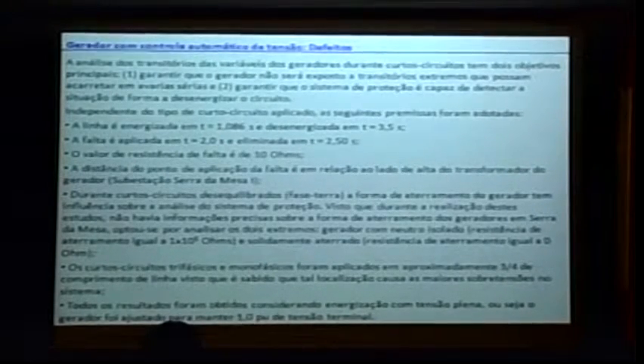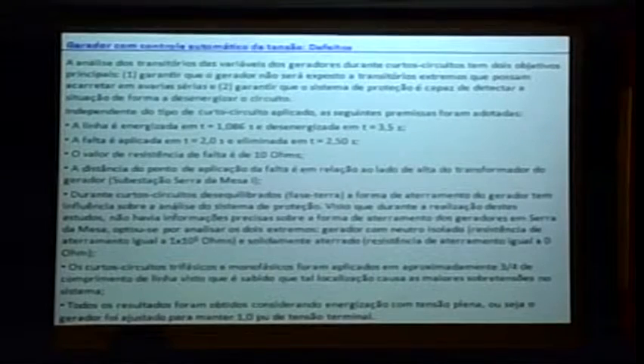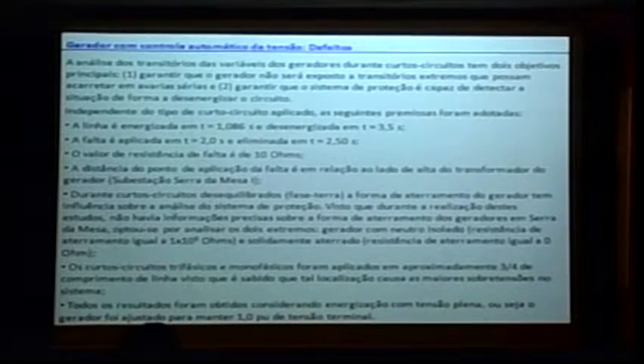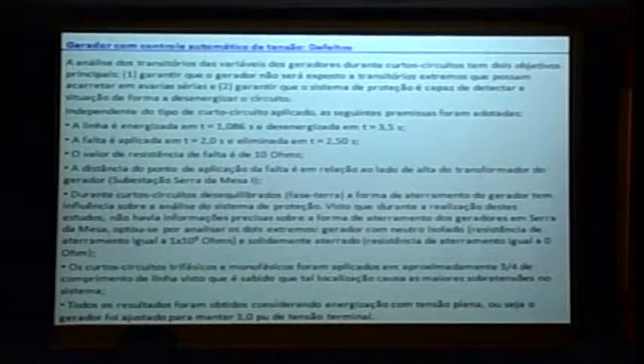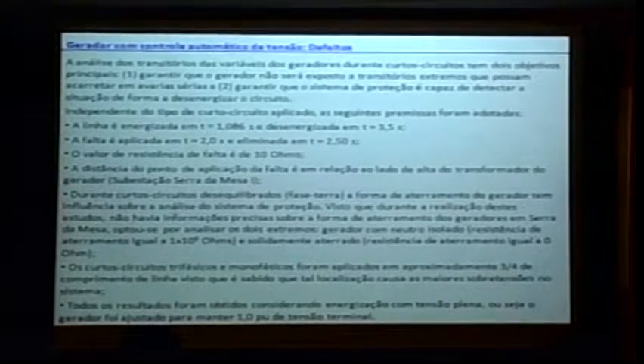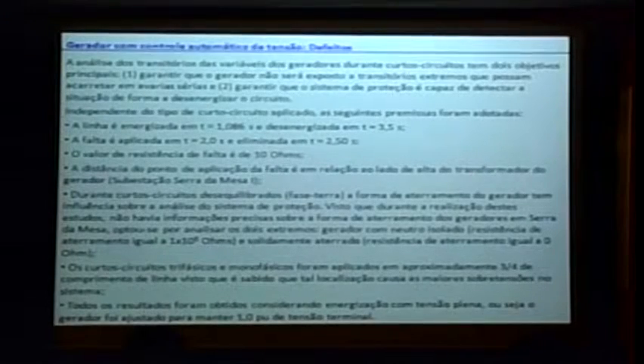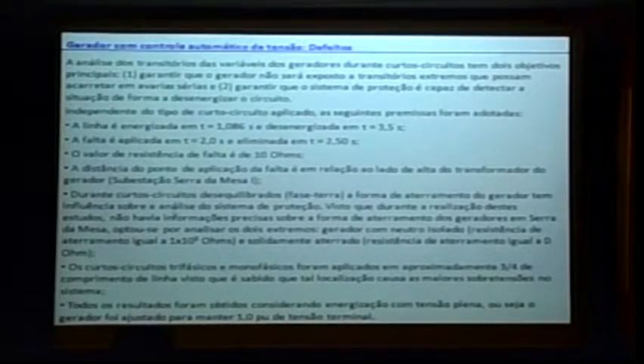During the energization, after a while you see that it stabilizes. You make a fault to see what happens to the generator in case, for instance, there were faults during the energization test of the line with half wavelength, single phase and three phase. That was the scanning of the whole extension of the line, but I'm going to show you here only around 3/4 of the line. The fault is always applied in 2 seconds and it's eliminated in 2.5 seconds. So we will keep the fault for 500 milliseconds, precisely to analyze what impact it has on the generator. Fault resistance used was 10 ohms.